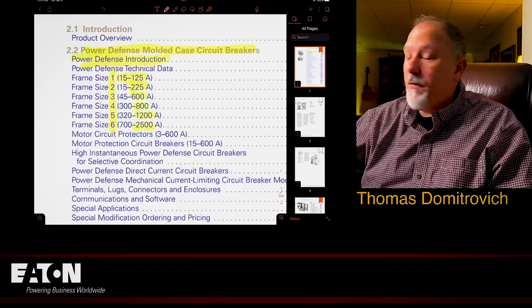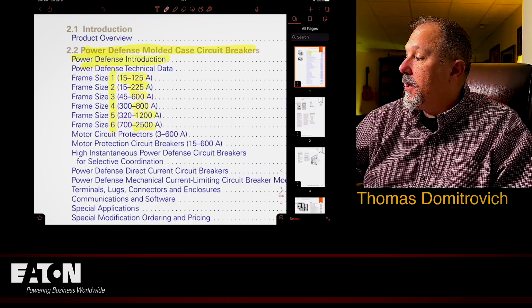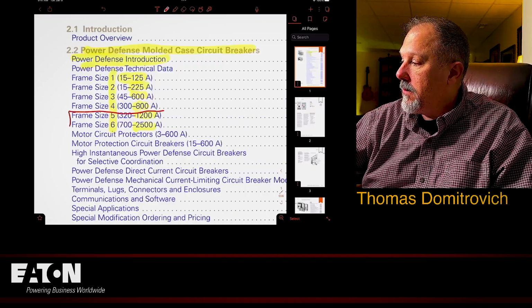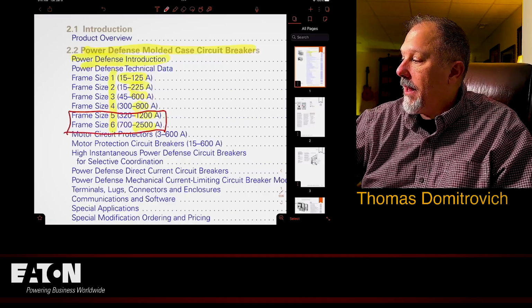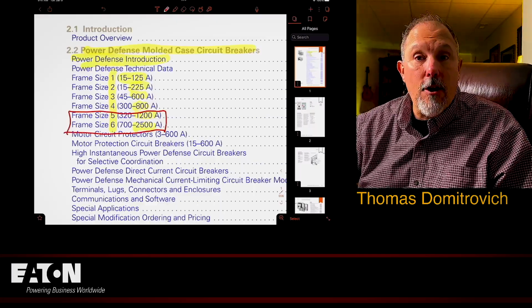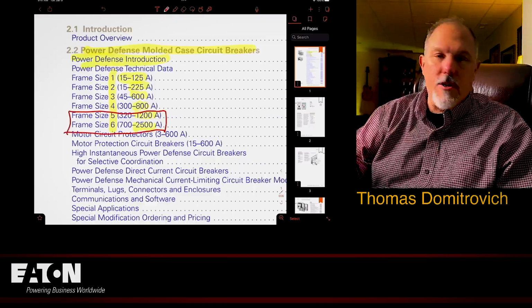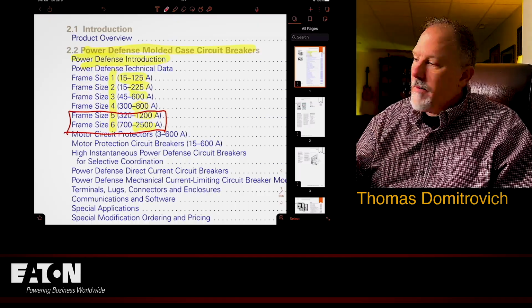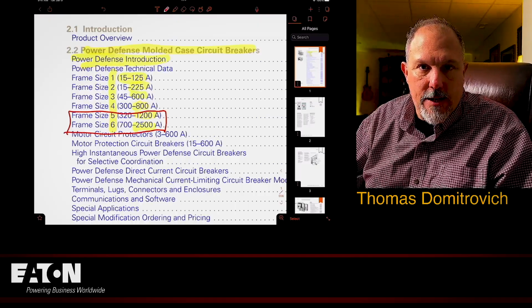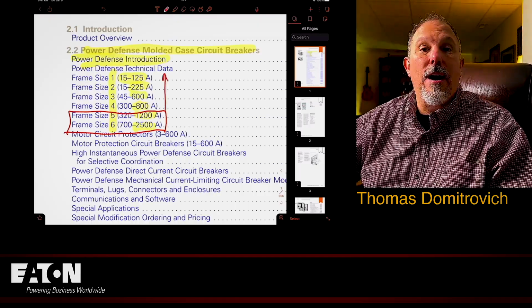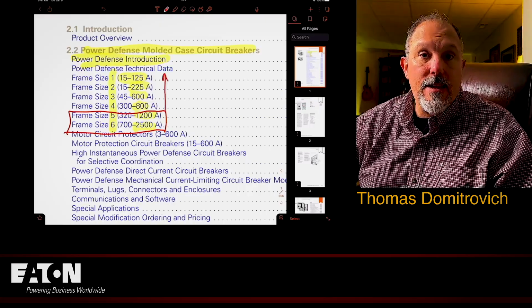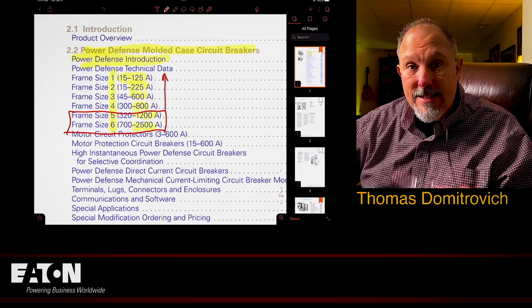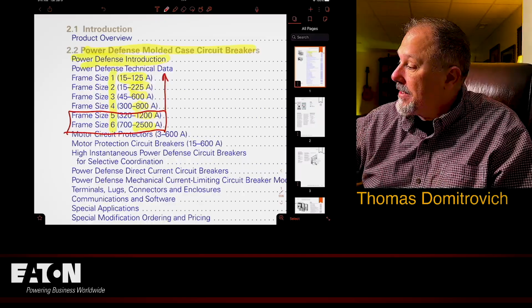Because of 240.87, all breakers 1200 amps and above have to have what? An arc reduction maintenance switch or one of those other technologies. Telling you, every one of these are going to have an arc reduction maintenance switch. The question we have is how small of a circuit breaker can we get that has that same technology on it? So let's take a look.